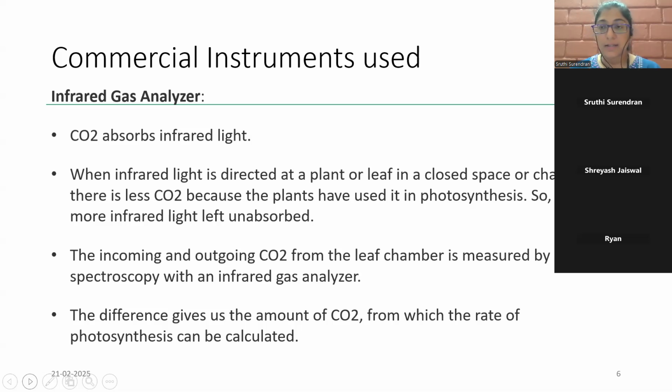So in an infrared gas exchange analyzer, infrared waves are passed through a chamber, and if the chamber has some carbon dioxide molecules in it, these carbon dioxide molecules absorb the infrared rays, and then the instrument measures the infrared rays which are not absorbed. Initially, they know the intensity of the infrared beams that they are sending into the chamber, and they also know that as a result of absorption, some of the infrared rays are absorbed. So what is the remaining infrared in the chamber? It is on the basis of this principle that infrared gas exchange analysis works.